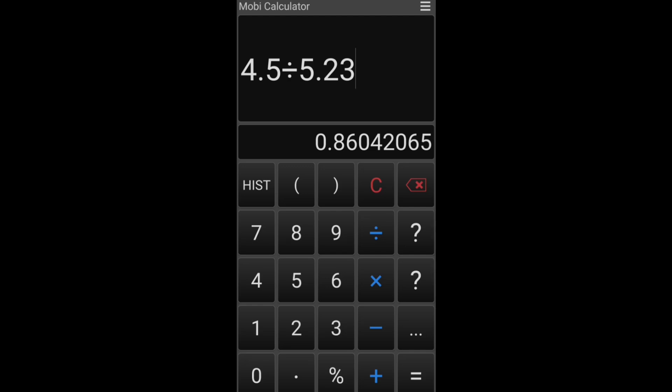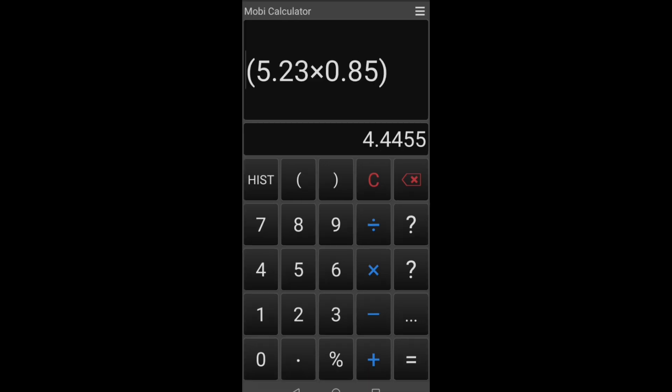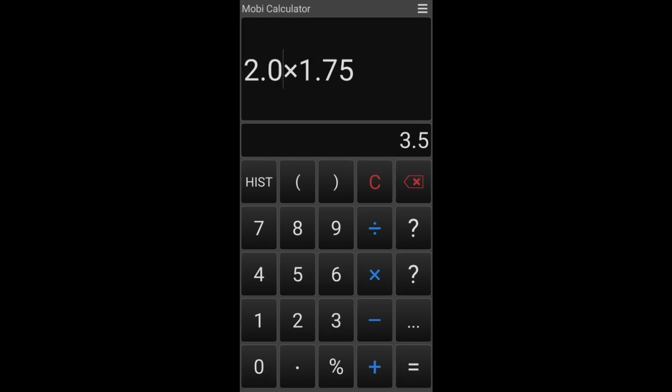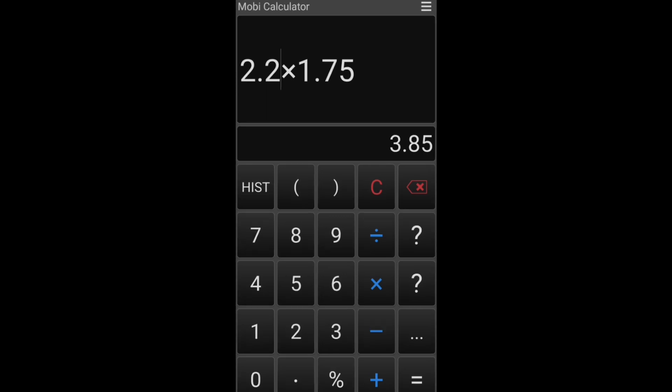Now for the boring bit. Or is it the best bit? 5.23kWh is the battery size. 4.5kWh is the energy that the app from GiveEnergy said that we took out of the battery. So that is 86%. That's pretty close to the 85% depth of discharge. So so far so good. The GiveEnergy stats agree. Yes, whichever way you look at it, 85% of 5.23kWh is roughly 4.5kWh. But what we know is, all we used was a 2kW heater for one and three quarter hours, one hour 45 minutes. That's 3.5kWh of usable energy. Even if we use the value of 2.2kW that we saw on the MyEnergy app for the one and three quarter hours, that's still only 3.85kWh, not 4.5kWh.